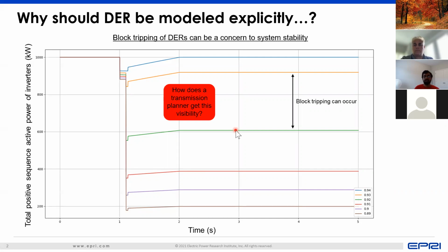But more so, if a transmission system event occurs, then you can have these distributed resources tripping in blocks. Essentially, if you have a very small change in the transmission system voltage, so you see here, if your voltage changes from 0.94 per unit to 0.89 per unit, which is essentially a 5% change in transmission system voltage, you can go from a state where all the DER are connected to a state where 80% of the DER trips out. And if this can occur over a wide enough area, then you have transmission system events that would usually not cause a trip in generation, but that will now happen, which means that transmission system planners have to have visibility of the tripping that can occur.